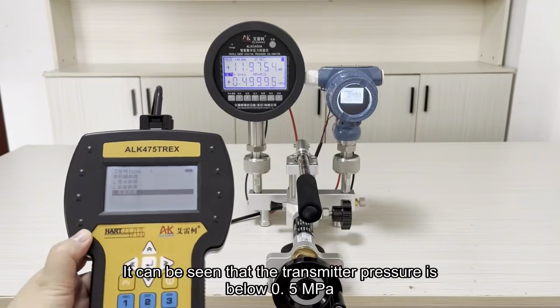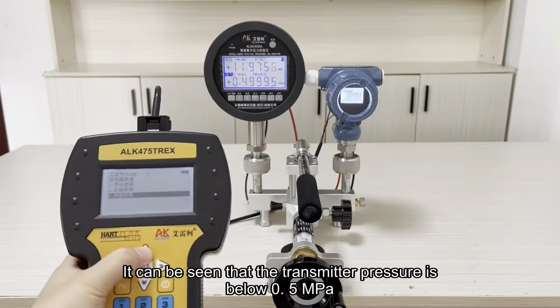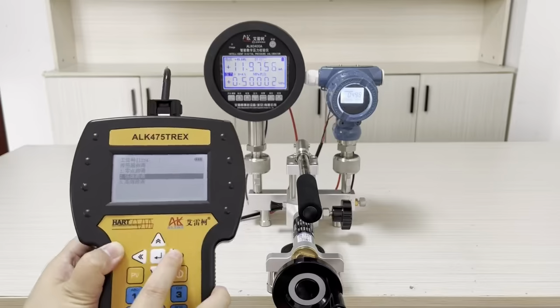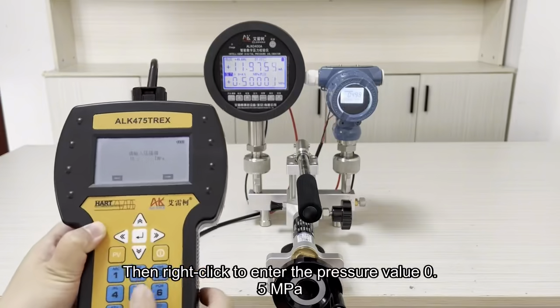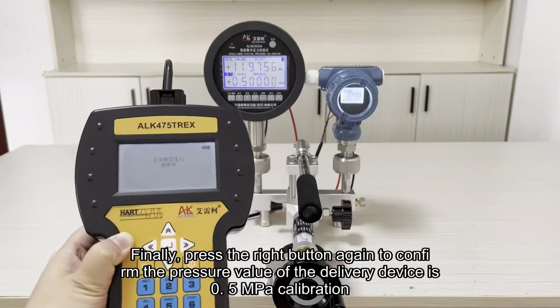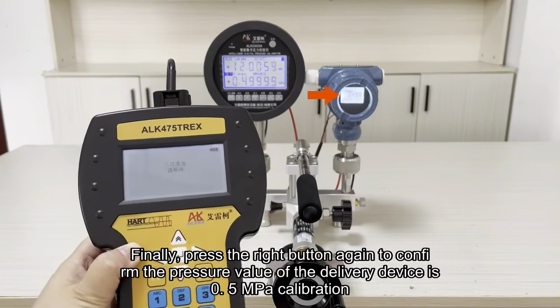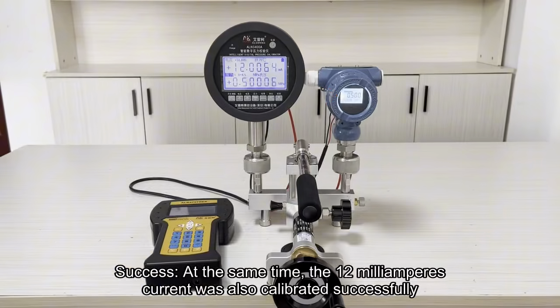It can be seen that the transmitter pressure is below 0.5 MPa, so choose low-end fine-tuning. Then right-click to enter the pressure value 0.5 MPa. Finally, press the right button again to confirm the pressure value of the transmitter is 0.5 MPa. Calibration success. At the same time, the 12 mA current was also calibrated successfully.